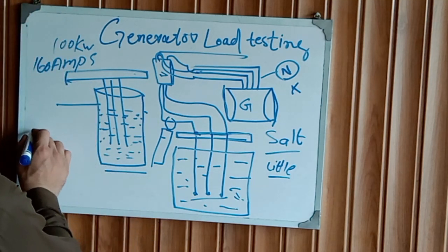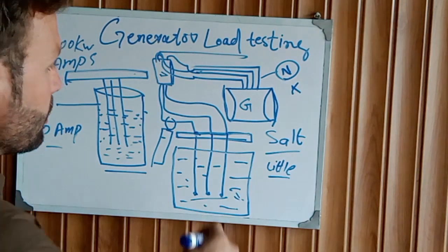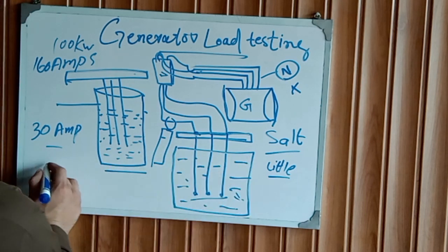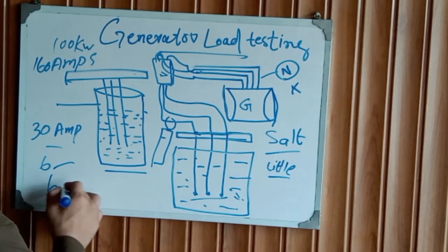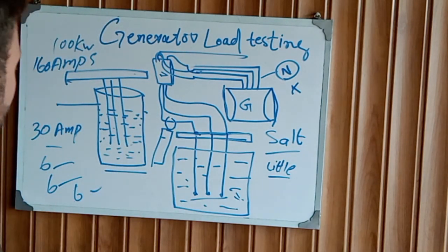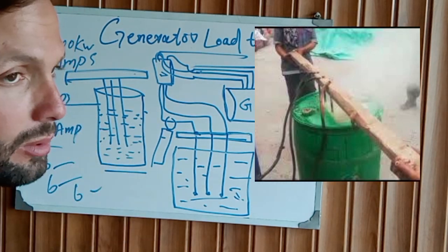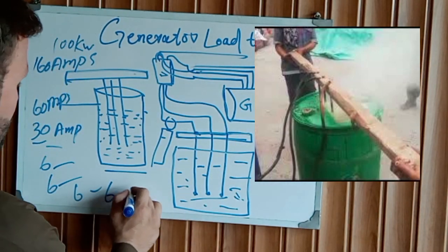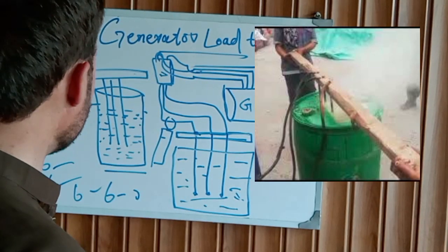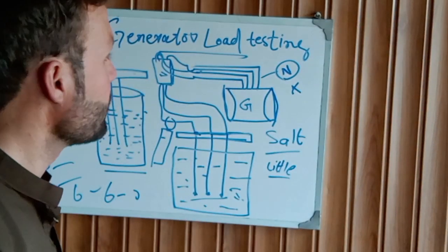If the load has reached 30 amperes, put some more salt — first 60 spoonfuls, then again 60 spoonfuls, then again 60 spoonfuls in the water. The generator will start carrying more load, and now the generator load will reach 60 amperes. Then put another 60 spoonfuls of salt and check the generator carrying the load — the load is going up. When it reaches 150 or 140 amperes, stop adding salt and check the load.